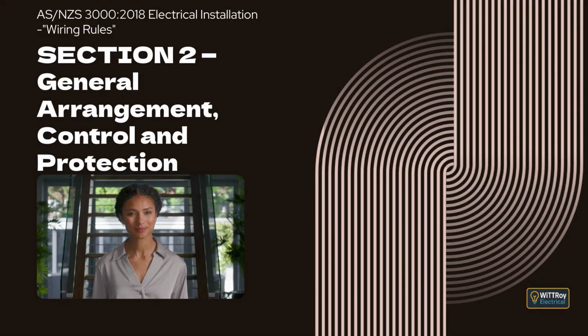Clause 2.5.3.3 Alternative position of overload protective device. This clause describes the conditions where the overload device may be placed somewhere other than the origin of the circuit. The first condition is that the conductor must have no branch circuits or socket outlets between its origin and the location of the protective device. This means there is no chance of supplying extra loads before the protection is reached.